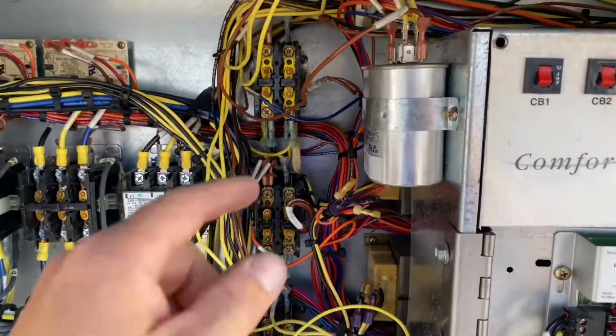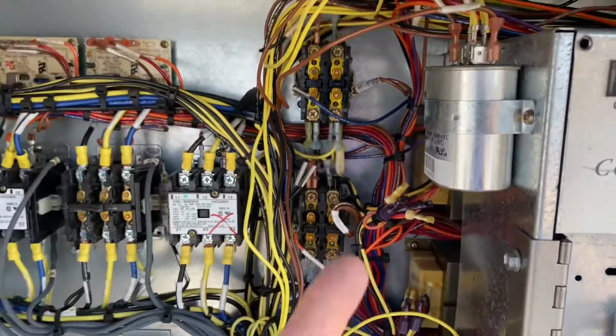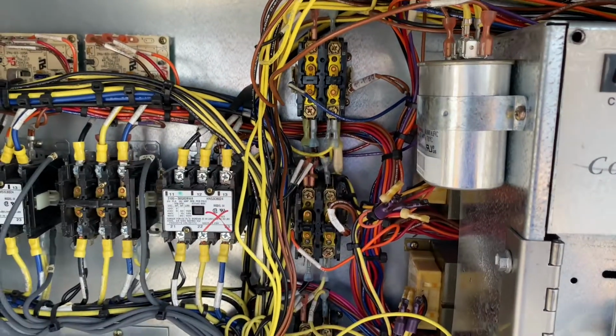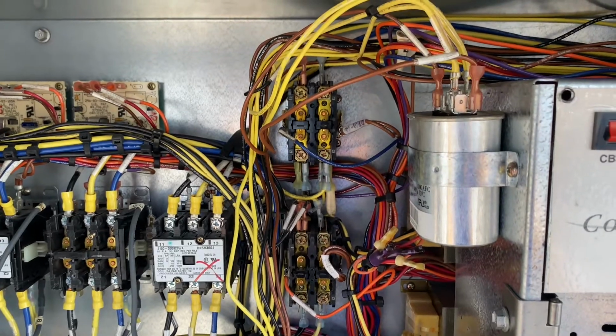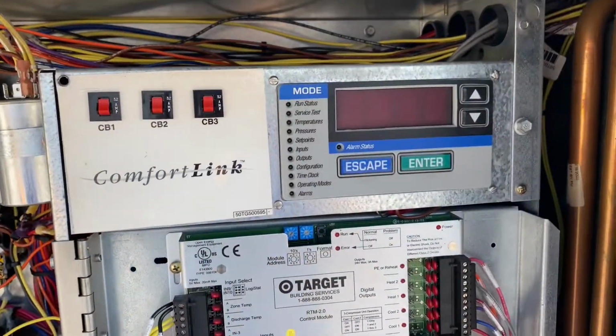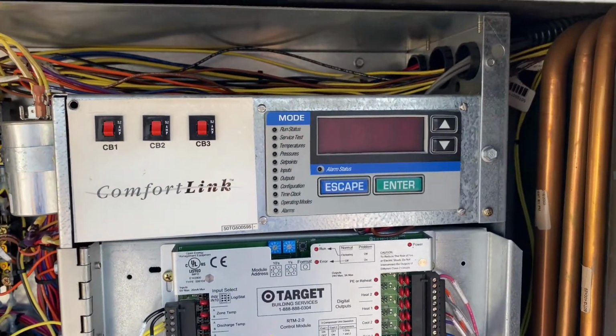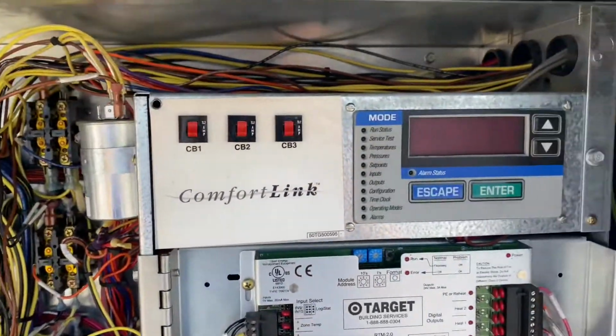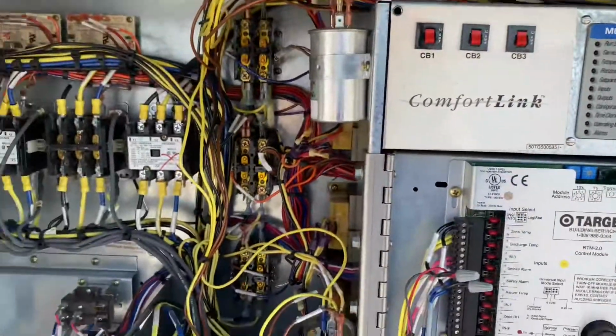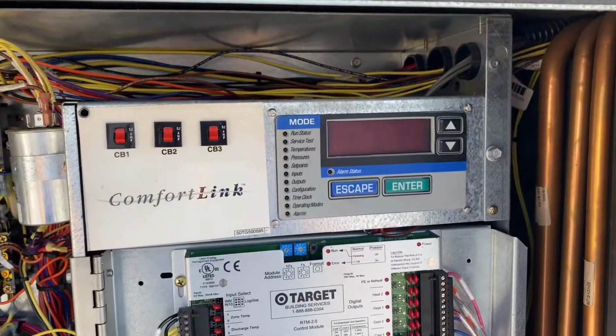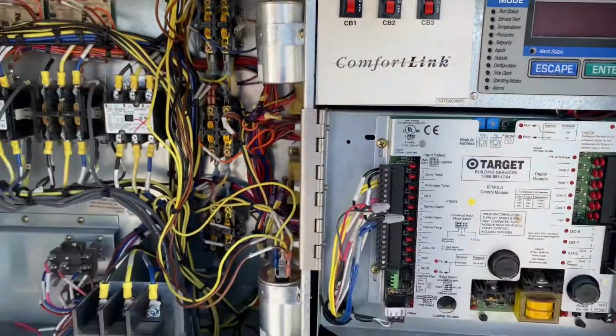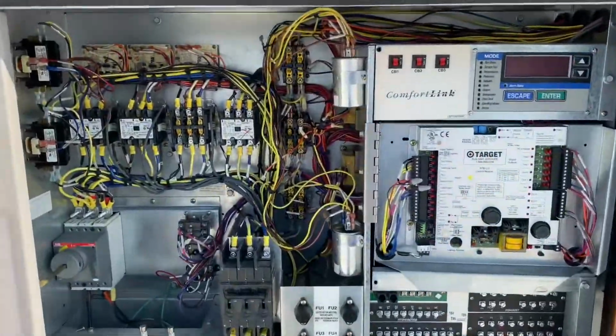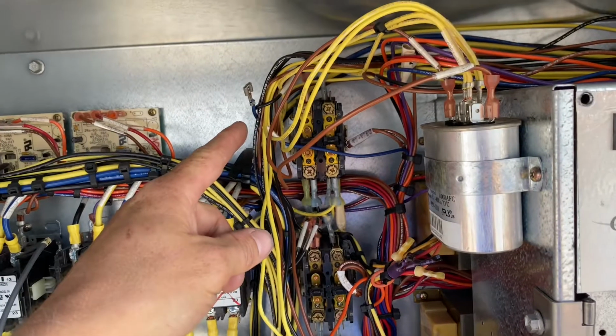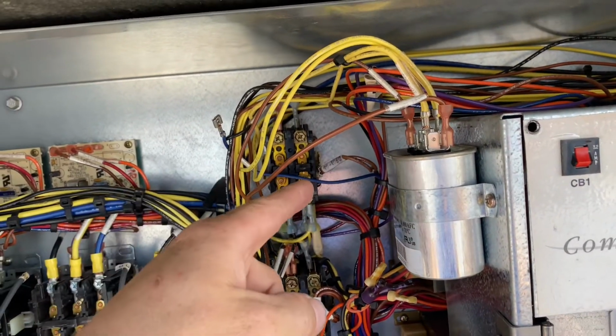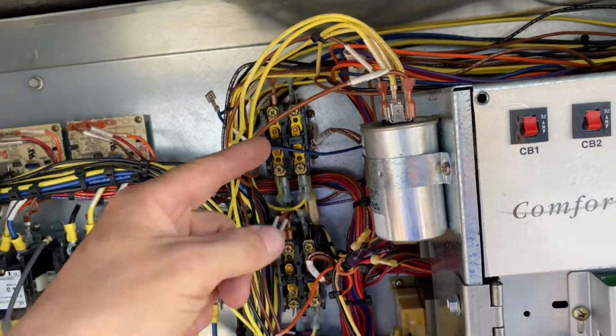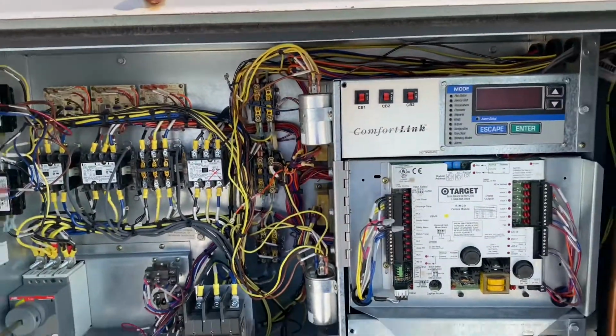So what I'm going to do now is kill power again, lock it back out. I'm going to go back to this contactor for outdoor fan 1. I'm going to pull the control power off of the contactor for outdoor fan 1 to not allow it to run. And then I'm going to come back and try out outdoor fan contactor 2 and contactor 3, which hopefully will run outdoor fans 2, 3, and 4, and we'll go from there. All right, so I unlanded one of the power wires for the coil, 24 volt, feeding the coil and the contactor for outdoor fan, or condenser fan, number 1.